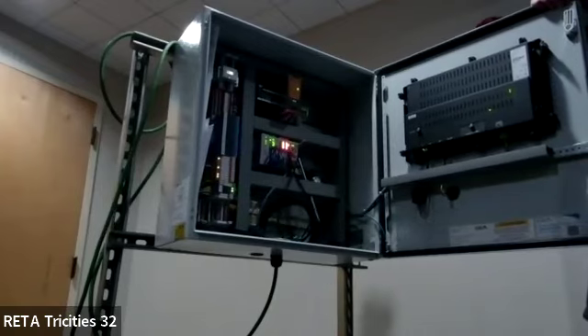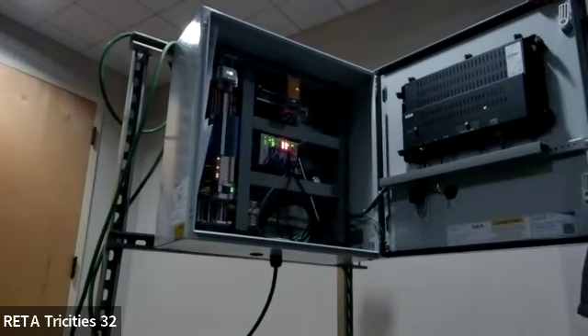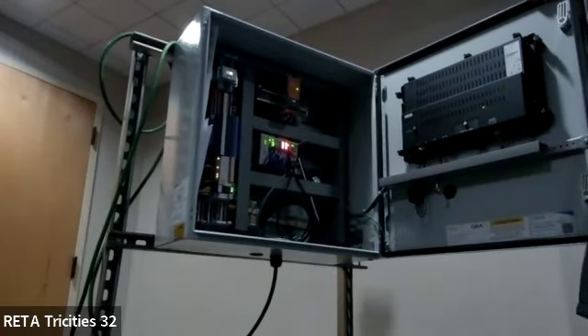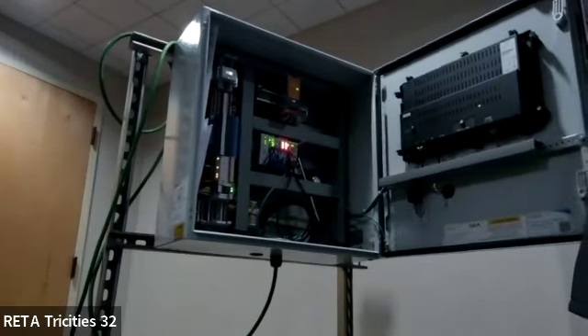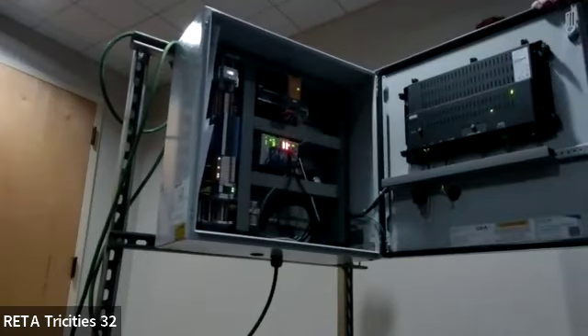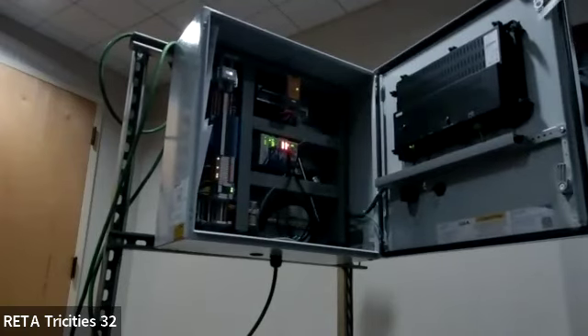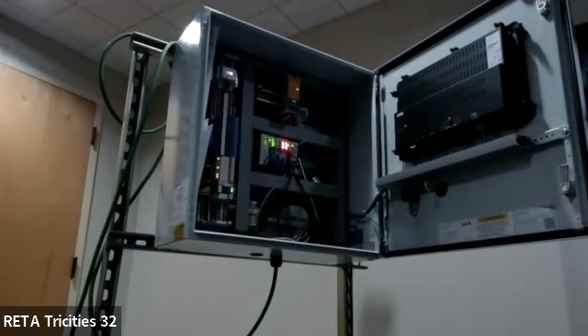What I would do before you change it, though, is plug a USB drive in and back up your configuration to the USB drive. Power down the panel, change the battery, power back up, upload your configuration. And if you do change out the processor, you'll probably have to re-download the configuration. Yep, you'll have to. That's why these panels all come with a USB drive in them. It's going to have everything this panel came with from GEA on it.